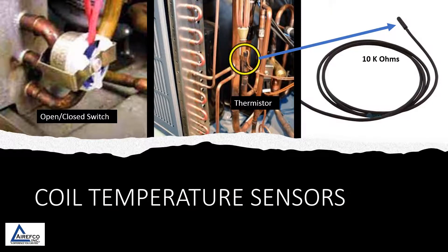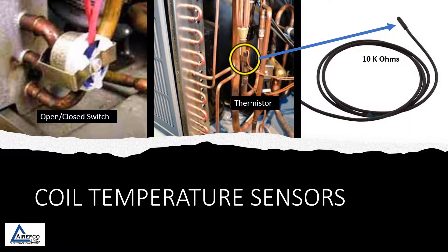The outdoor coil temperature is what drives the defrost cycle — it tells the defrost control board that the coil is cold enough to freeze up and needs to go into defrost. This coil temperature is sensed by two different devices. The first is a klixon switch, which is normally open and closes when the coil reaches a certain temperature, signaling the defrost board to initiate defrost. The second is a 10k resistance thermistor on the right, which also senses coil temperature. Both devices should be checked during troubleshooting to ensure the klixon switch closes when it should and the thermistor is within range.